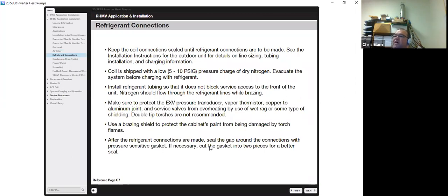Refrigerant connections: make sure you keep your coils sealed until the refrigerant connections are made. The coils are shipped with a low 5 to 10 psig pressure of dry nitrogen. Evacuate the system before charging with refrigerant. Install refrigerant tubing so it does not block service access to the front of the unit. It's very important that if you're installing it, the service guy at a later date can access it easily without having to disconnect lines.